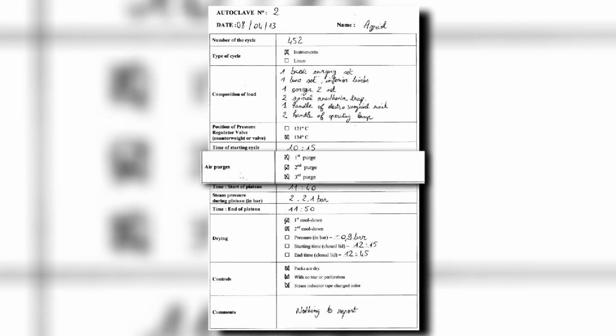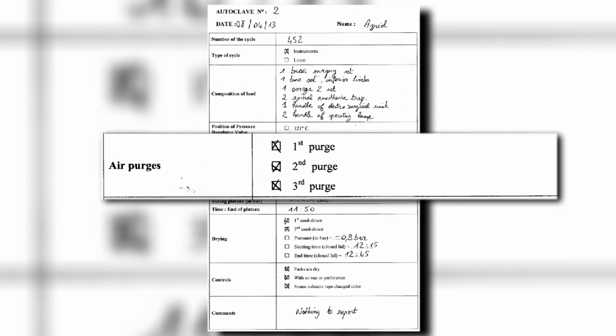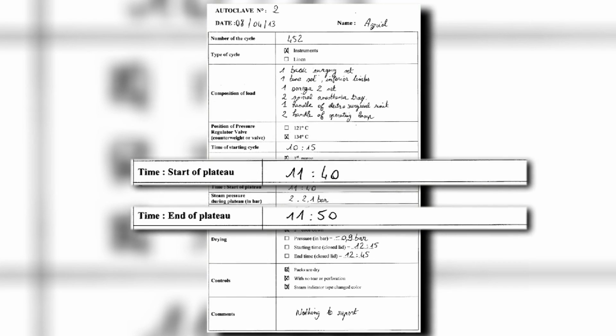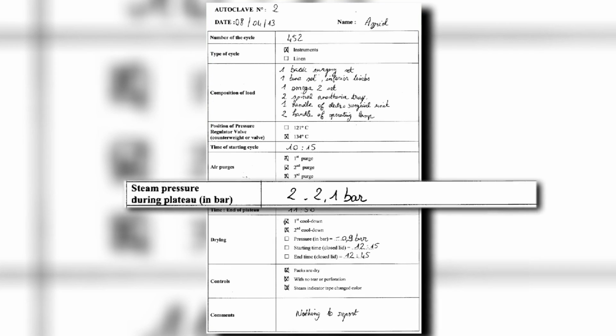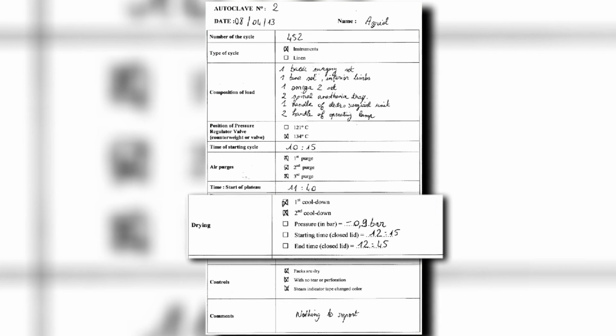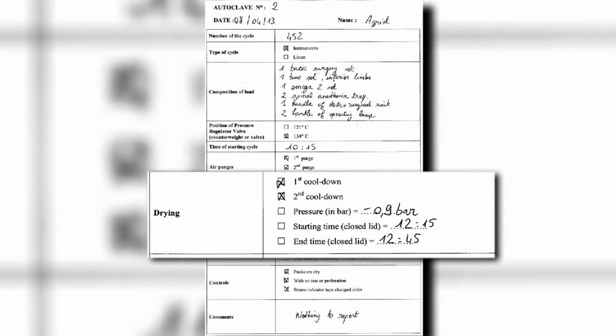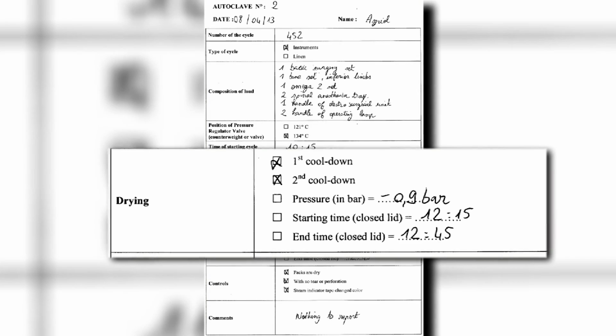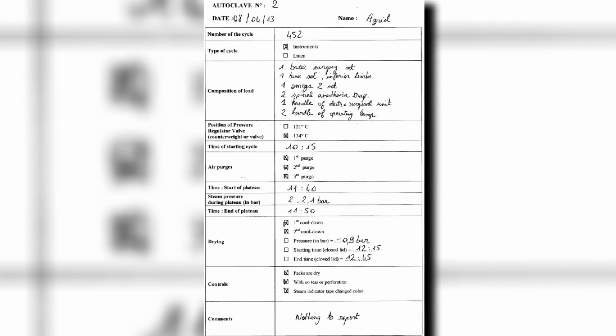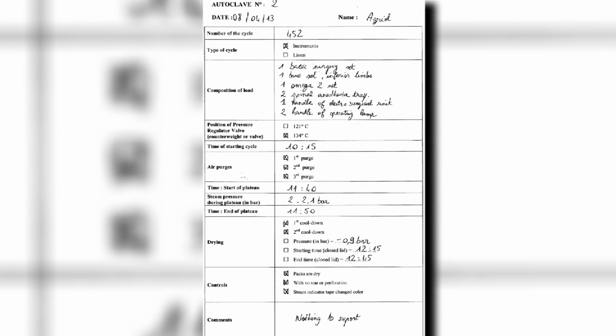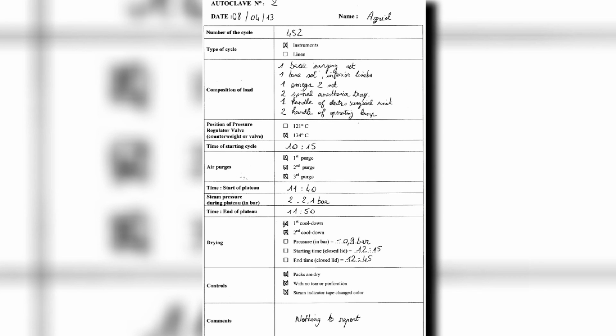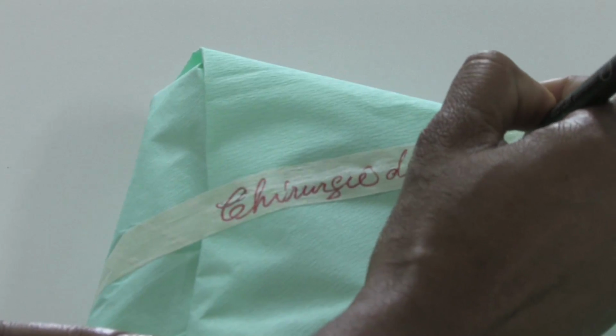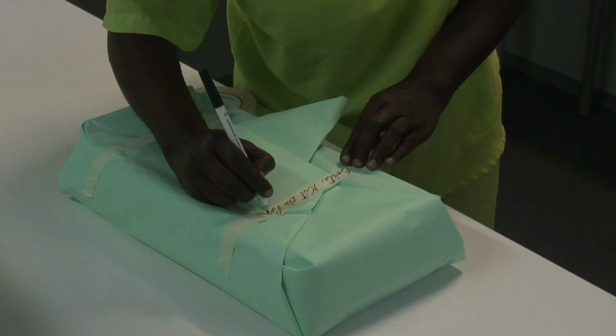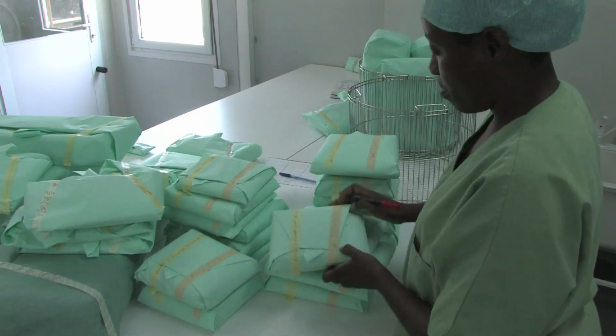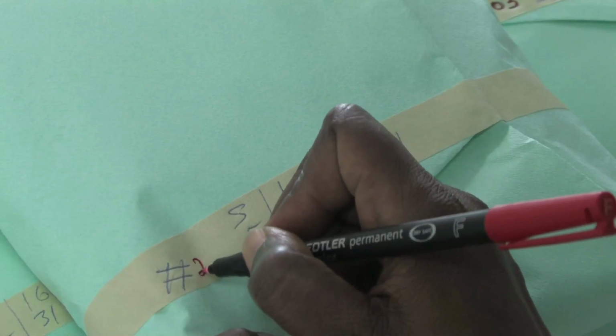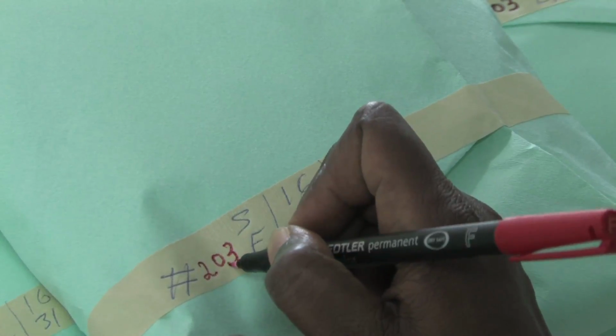Then each step conducted is entered, the first, second and third purge, the plateau and its duration, the pressure reached, the first and second addition of water for cooling, the negative pressure achieved, and the drying time with the cover closed. This sheet should make the work easier and prevent steps from being forgotten, especially when there are several autoclaves operating at the same time. Traceability of the pack should make it possible to connect each instrument set used for a patient to the autoclave cycle in which it was sterilized. That is why the cycle number is written on the autoclave indicator tape.